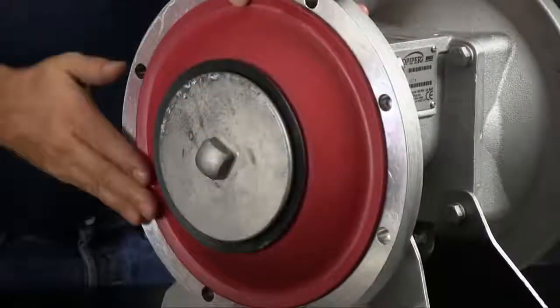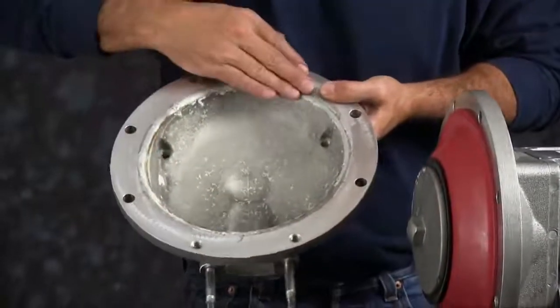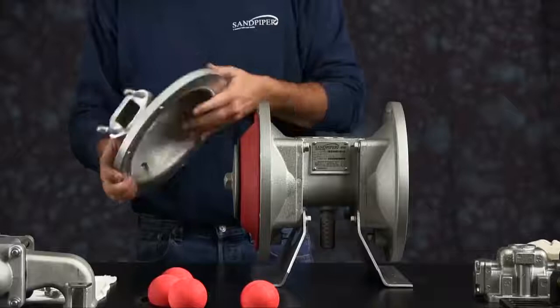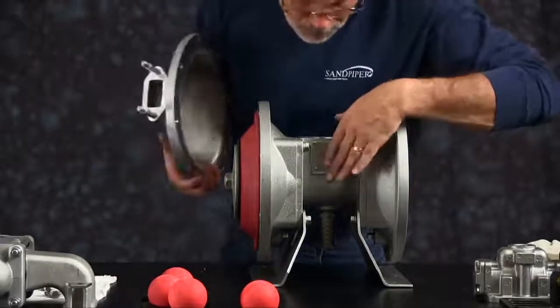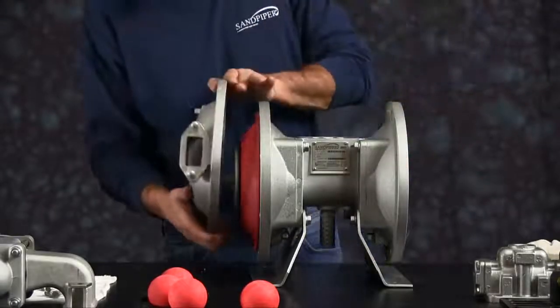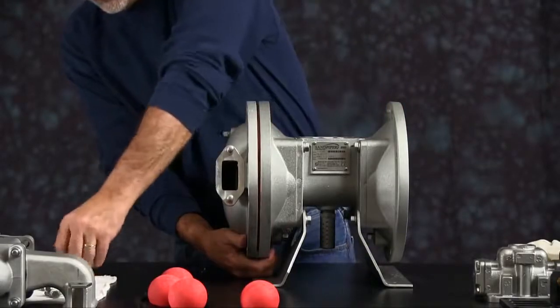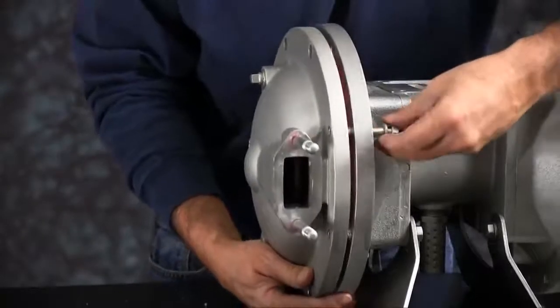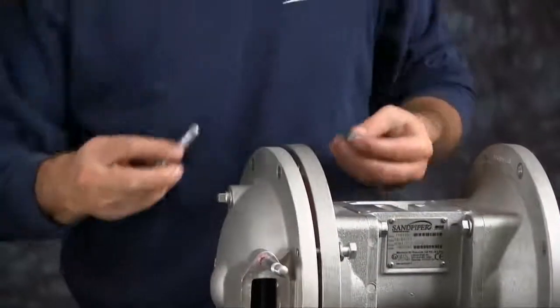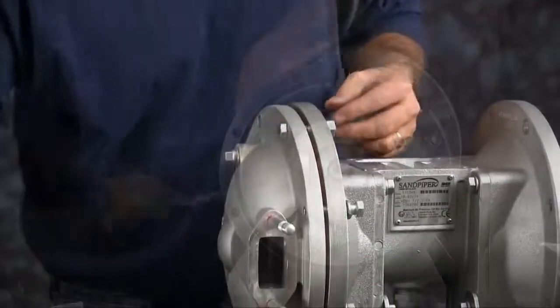Inspect the outer chamber for casting integrity. Inspect the machine faces and radius of the chamber for damage or material buildup. Scarring, scratches, or material buildup can be cleaned up by using emery paper, crocus cloth, or fine sandpaper. The port side of the chamber faces in the same direction as your name plate. Install the two blind hole bolts first — this will hold the chamber in place while you install the rest of the bolts. Install the rest of the bolts and tighten them down in a crossing pattern.